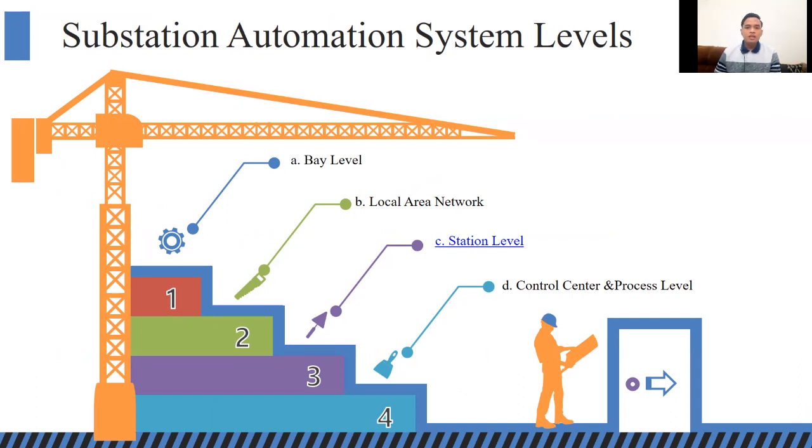The IEDs are directly connected to switchgear without any need for additional interposing or transducer. Each bay control IED is independent of the others, and its function is not affected by any faults occurring in any of the other bay control units of this station.